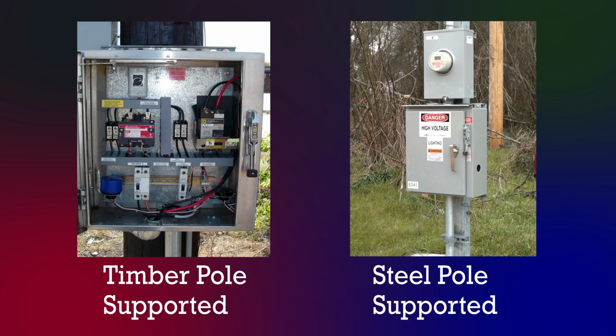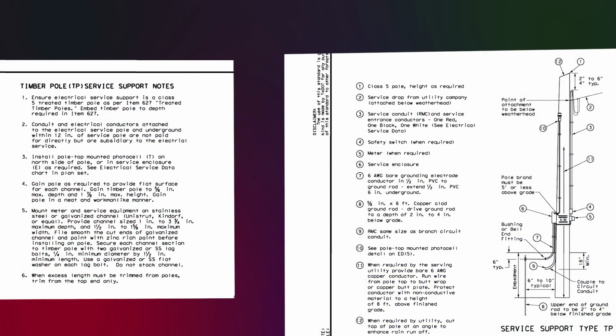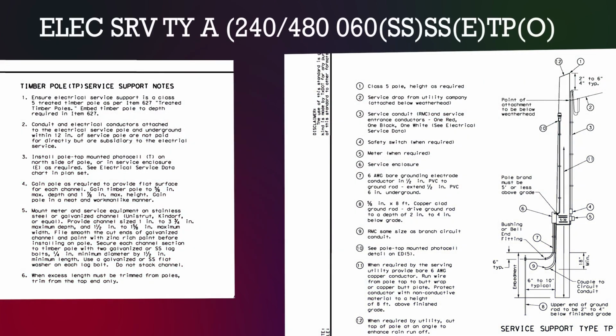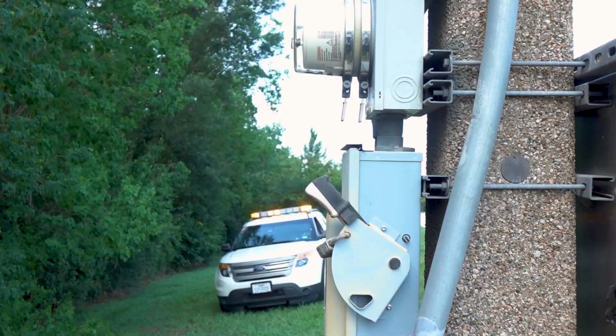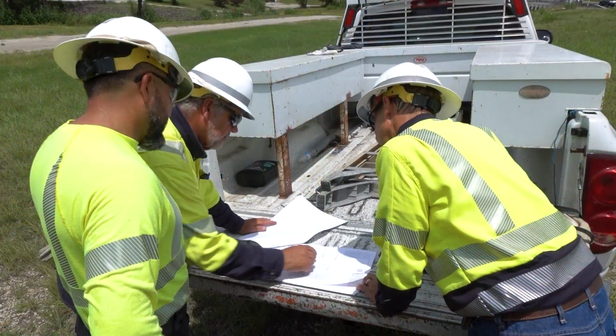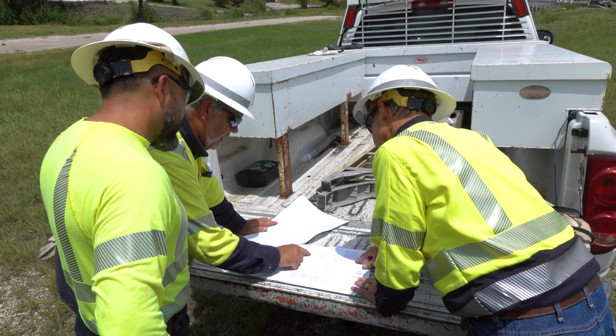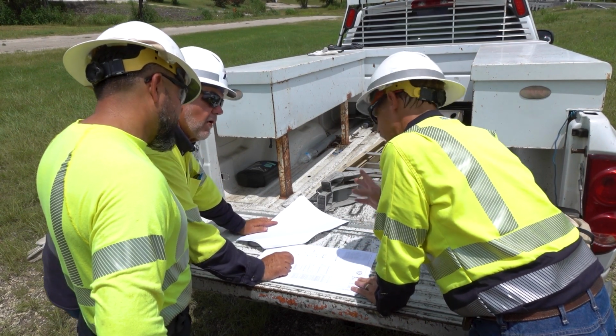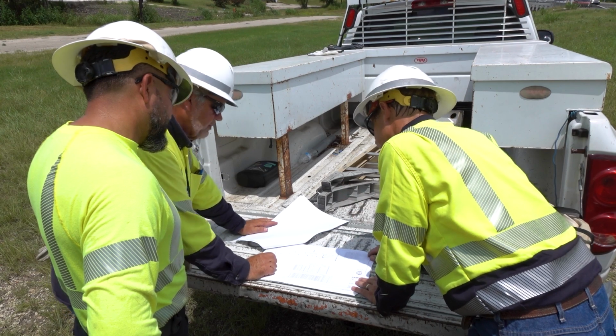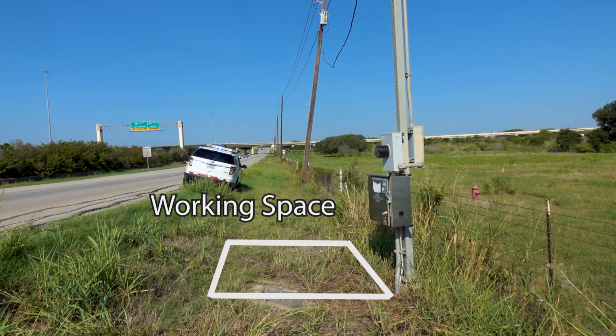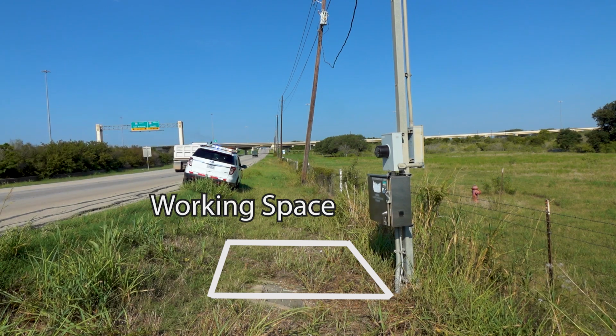When a timber pole is called for by the descriptive code, the pole is to be gained or notched in accordance with the details listed on the left side of the ED10. There are several other support structures that can be specified by the engineer, and the inspector must review the requirements of each, which are detailed on the standard sheets relating to each type of support, ED7, 8, 9, and 10. The inspector will need to confirm that the NEC-required clear working space in front of the service has been provided, and that there are no obstructions in the work area in front of the service.